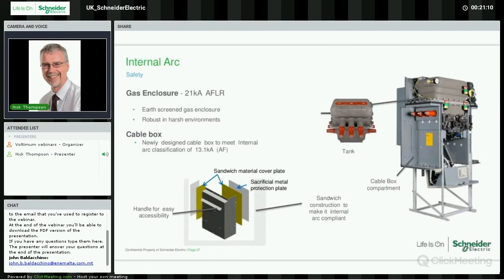And then we've got the cable boxes, not only the ring switch cable boxes, but also the circuit breaker cable box as well. And they were tested at a lower level, whereas the fault levels on the ring would tend to be a lot lower inside the cable box than potentially we would see inside the main gas enclosure. Now, the designation we've got there against the gas enclosure AFLR is A for authorised, F for front, L for lateral, and R for rear. It's down to the manufacturer what designation we would put against that, and that will be clearly marked on the rating plate on the unit. Now, for the cable boxes, the designation for that is AF with a much lower fault level.